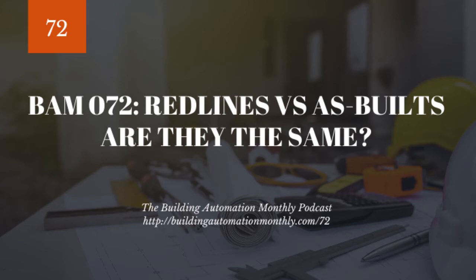So you've got all that, and then each one of them has a final mechanical drawing. Well, which one is the right final mechanical drawing? Well, if the mechanical is saying his drawing's right and all these other subs are under him, whose drawing do you think he's going to go with? Now, he's not going to go with the BAS guy's drawing. He's going to go with his own drawing. He doesn't want to do extra work. He's going to say, yep, these are the as-builts. Here you go, Mr. GC. Take them and run with them. And that is why I hate when individual subcontractors create their own as-built.